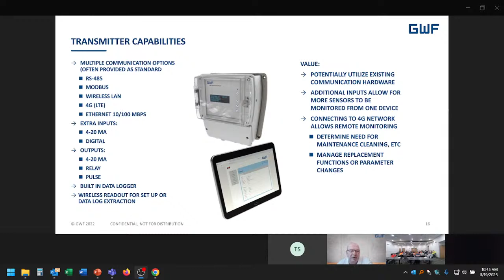So by having lots of options, using these devices these days means that you can potentially use existing communication hardware or methods. You might not need to upgrade SCADA systems for a new device. Having more inputs, as I mentioned, allows you to have more sensors monitored from one device. And now the thing which I find most interesting and often turned down by utilities is the ability to connect these devices to, say, a 4G cellular network, which allows monitoring in various ways. It will allow us to help tell you if there's a need for cleaning, maintenance, or even manage a replacement function. So if a sensor has stopped and it's changed how it's measuring, being able to manage that remotely again becomes very powerful.